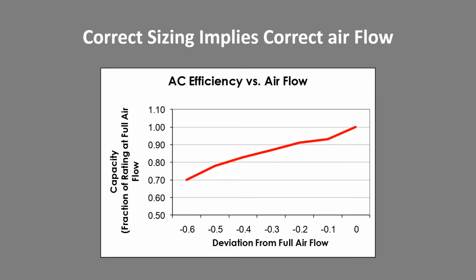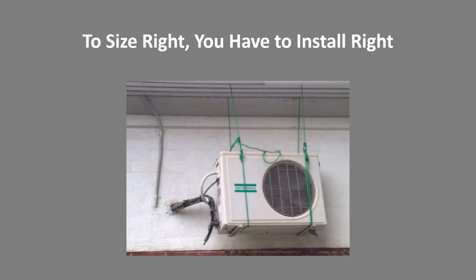And one of the biggest problems in heat pumps, as we all know, and air conditioners, is low airflow. This chart right here, if we start over here at 0 deviation from full airflow, basically we're saying we're getting 100% of the capacity. As we get down, say 20% low, we only have 90% of the capacity and 90% of the efficiency. And as we go down, we see that both the capacity and efficiency decrease as the airflow decreases. If you sold somebody, say, a 14 SEER air conditioner or a 10 HSPF heat pump, if you do not have the correct airflow, they're not going to hit that goal. So once again, to size right, you have to install right.